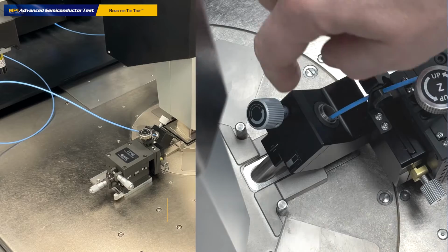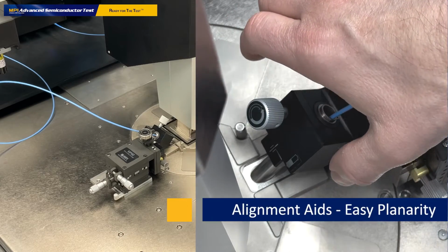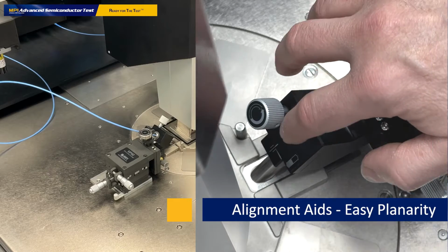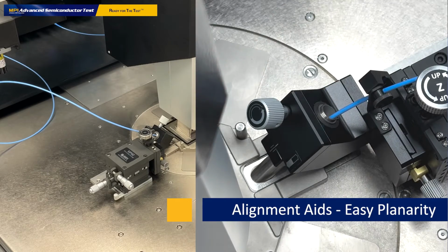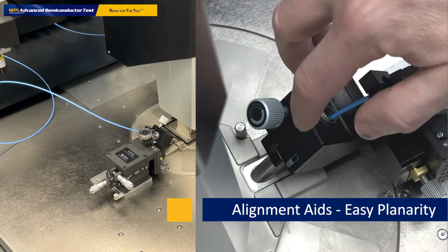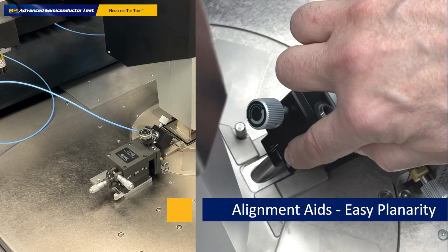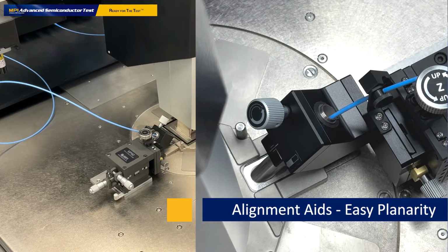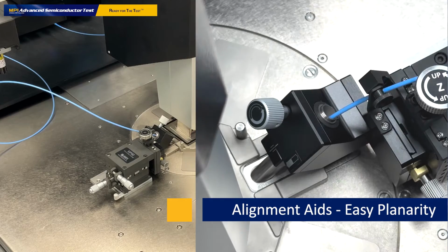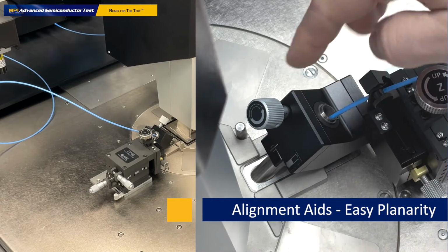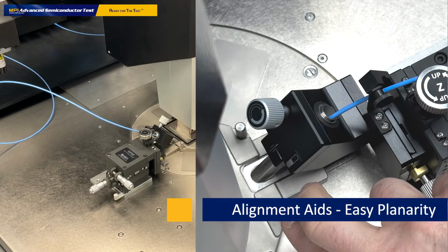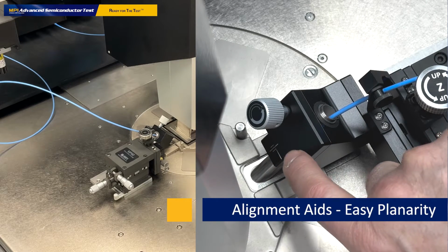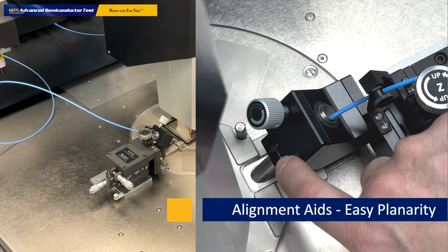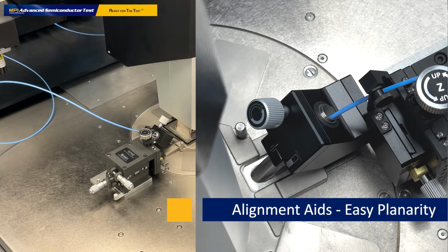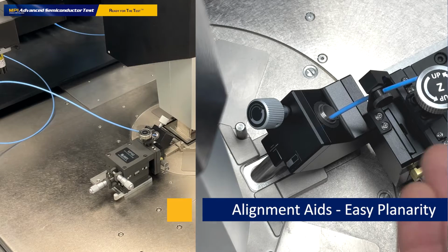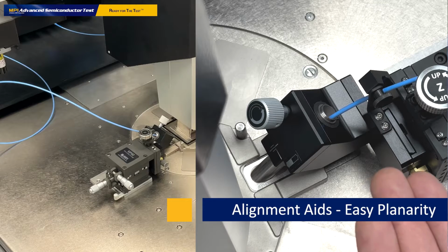All right, on the close view of the probe arm from the MPI micropositioner, we can see supporting marks which help us for the initial planarization of the probe. There is one reference mark on the probe arm itself, and three orientation marks which are placed on the mechanical feedthrough of the probe arm. What we can see here right now is that the central mark as well as the location mark or reference mark are perfectly aligned to each other, which means that the position of the probe arm is parallel to the chuck surface.